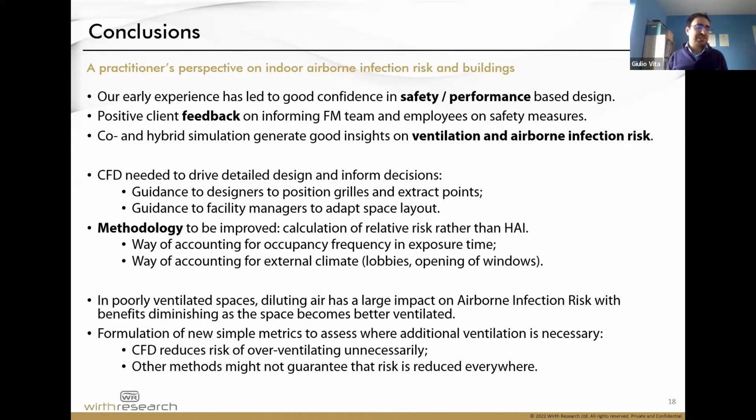But what we can say with quite enough confidence is that in poorly ventilated spaces, increasing ventilation does have a positive effect. Whereas if you already have a good, well-ventilated space, increasing ventilation or dilution might probably not be the solution because the system is pretty much insensitive to changes in viral loads and activities.